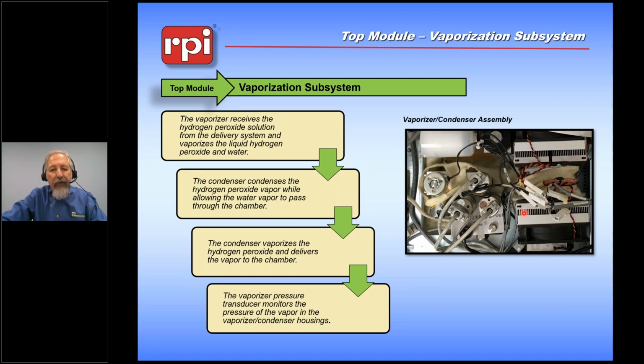That vapor is then transferred into a series of metal bars that run through the middle of this condenser assembly. And these thermoelectric modules can be controlled at very specific temperatures. And we basically condense out the hydrogen peroxide away from the water, thus concentrating it. Then we take the water and we send it away through this vaporizer condenser assembly into the chamber, out through the pumping system and into atmosphere, getting rid of it, taking the 59% hydrogen peroxide and concentrating it down to 90% before we then transfer the hydrogen peroxide through a series of valves into the chamber itself.